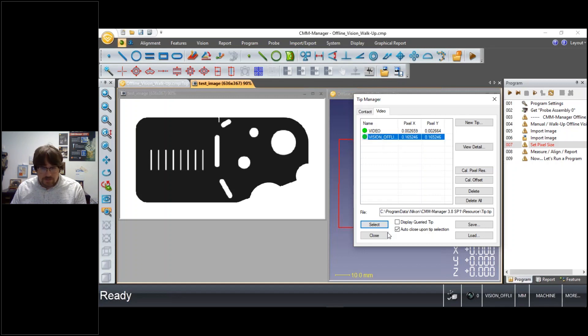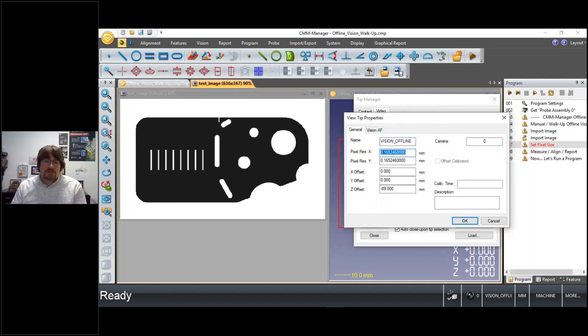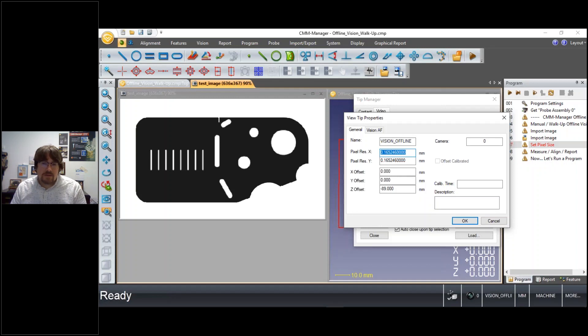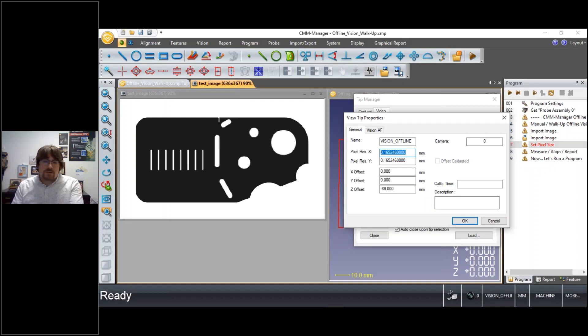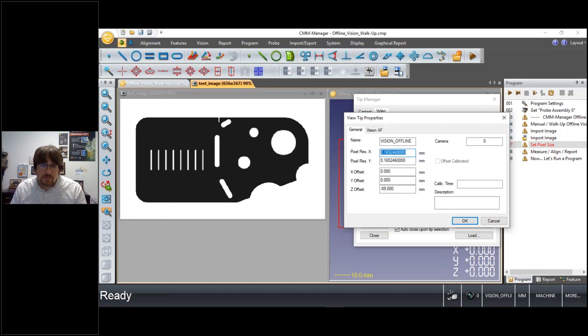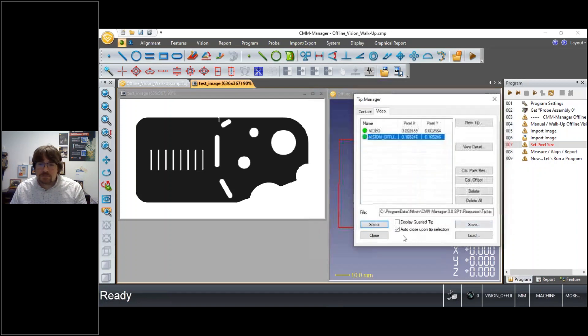So when you're using offline images, you do need to know the pixel resolution from that offline image. If you don't have that information inside of your image that you've gathered, you could include some artifact of a known size and perform the calibration immediately in CMM Manager and of course make the adjustment to the pixel resolution.